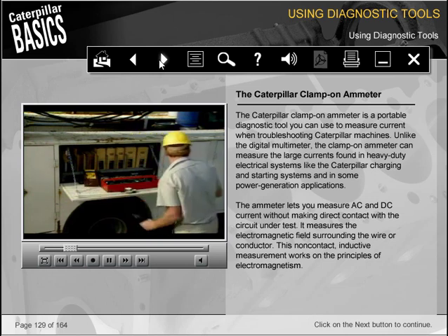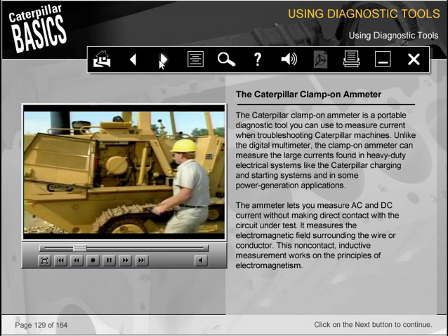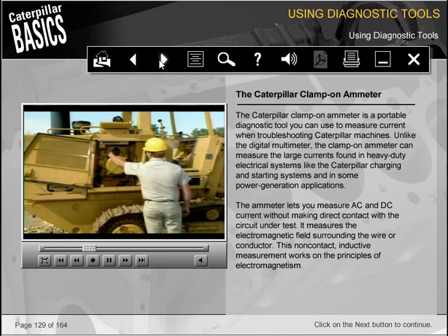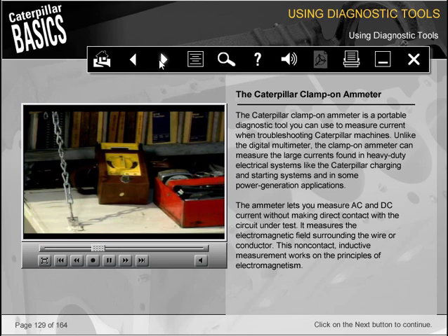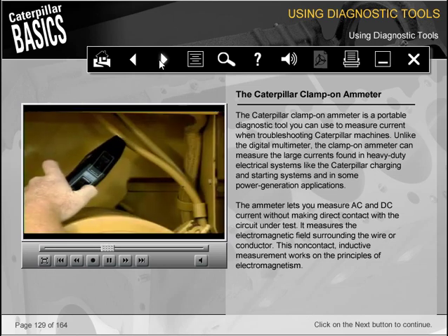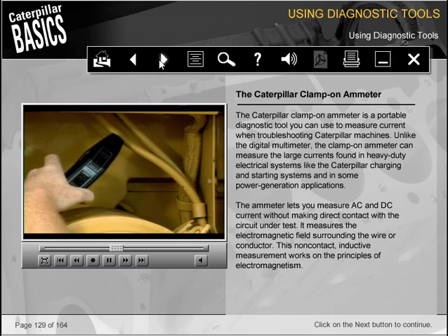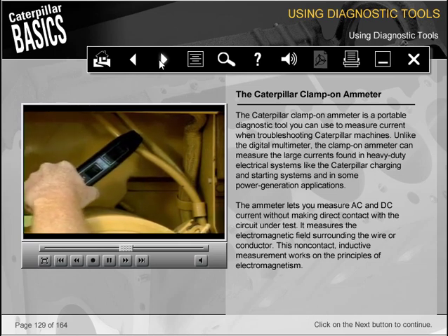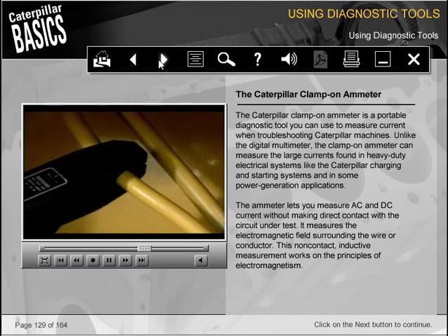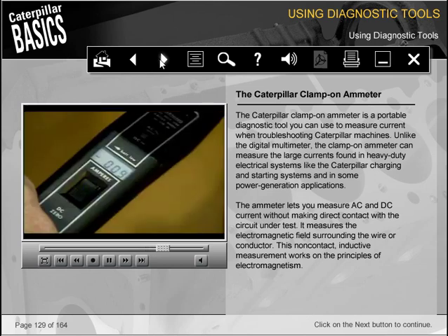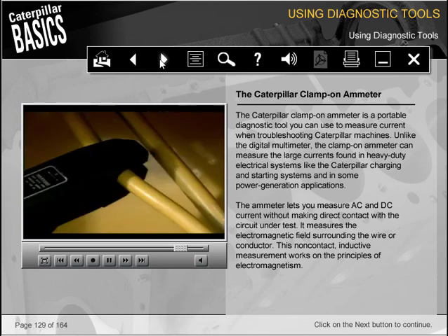The Caterpillar clamp-on ammeter is a portable diagnostic tool you can use to measure current when troubleshooting Caterpillar machines. Unlike the digital multimeter, the clamp-on ammeter can measure the large currents found in heavy-duty electrical systems, like the Caterpillar charging and starting systems, and in some power generation applications. The ammeter lets you measure AC and DC current without making direct contact with the circuit under test. It measures the electromagnetic field surrounding the wire or conductor. This non-contact inductive measurement works on the principles of electromagnetism.